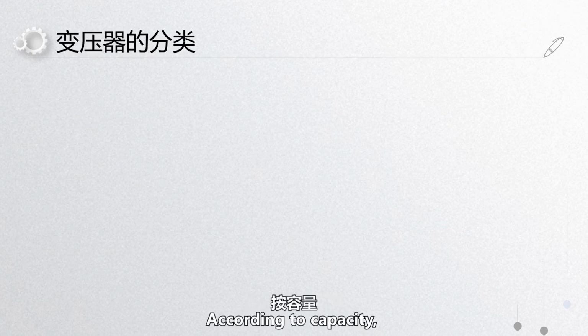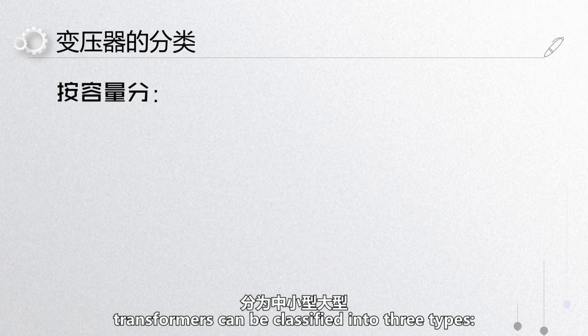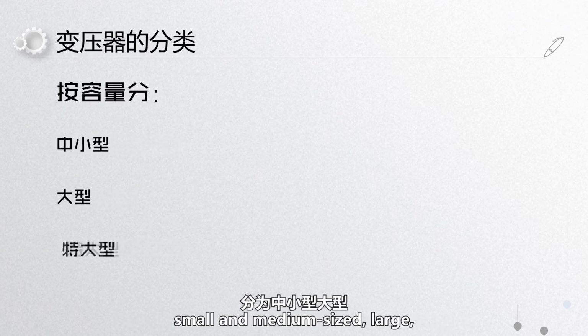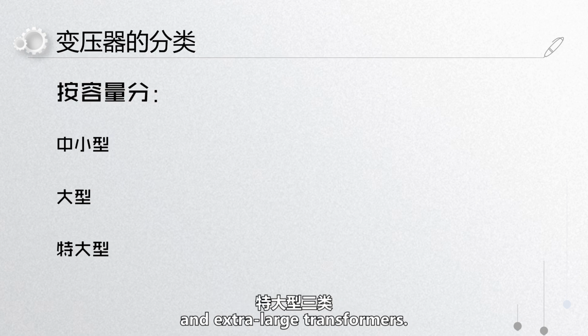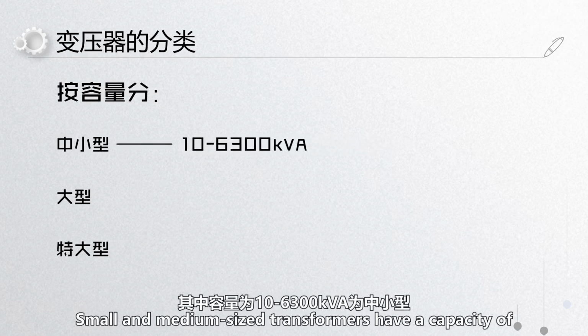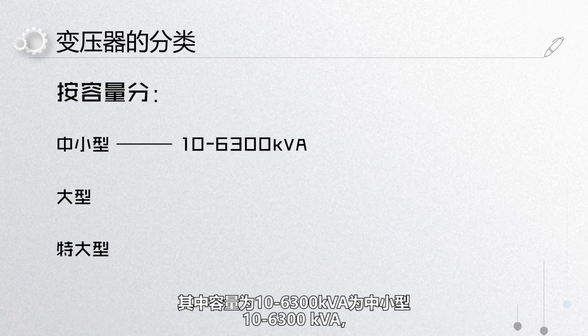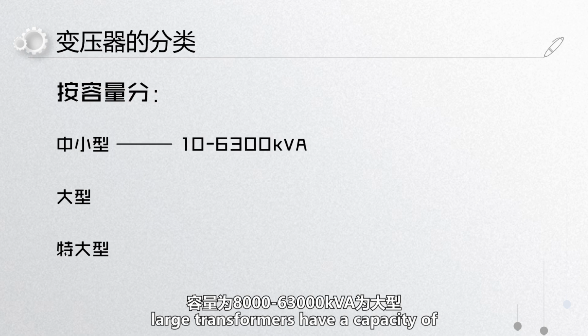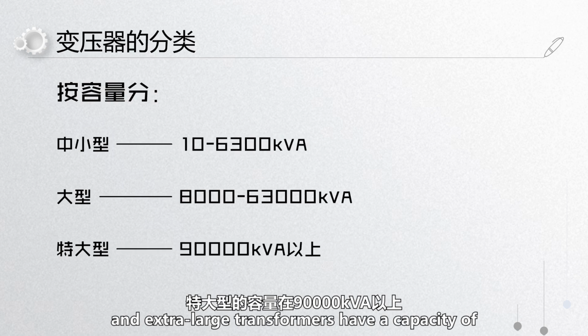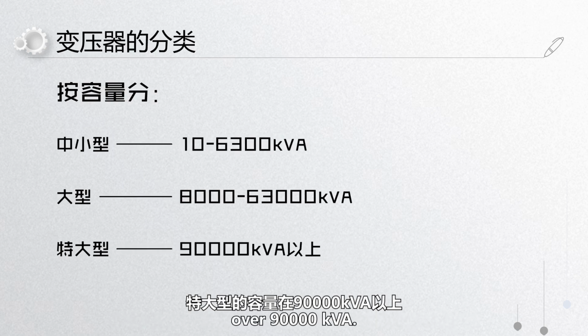According to capacity, transformers can be classified into three types: small and medium-sized, large, and extra-large transformers. Small and medium-sized transformers have a capacity of 10 to 6,300 kilovolt-amperes. Large transformers have a capacity of 8,000 to 63,000 kilovolt-amperes, and extra-large transformers have a capacity of over 90,000 kilovolt-amperes.